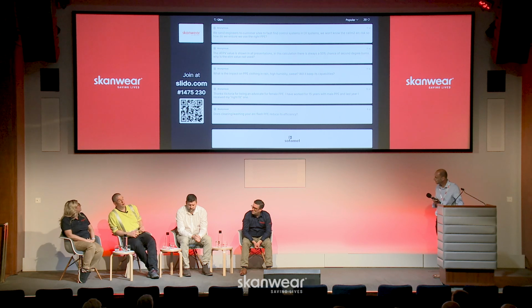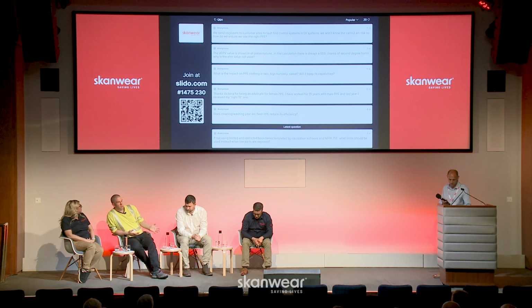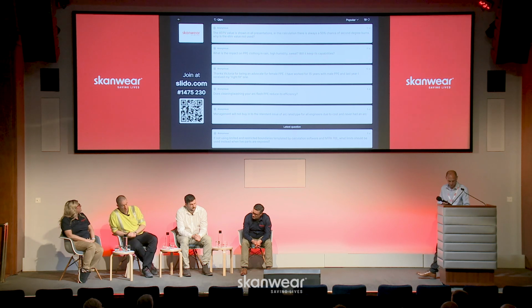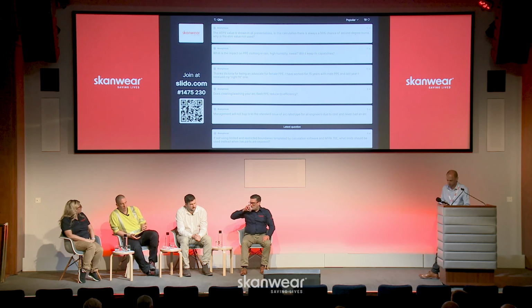Basically, I covered it when I was speaking earlier. We can use the tables from documents out there, NFPA 70E, CSA Z462, the European Arc Flash Guide's got some fantastic tables as well. There's also an online fuse table calculator which spits out data very quickly. Alternatively, having done this a long time, I've got a stick drive full of scenario-based studies, typical transformer sizes, run using ETAP, with different levels, different transformer sizes, different protection, ultra fast, and so on.